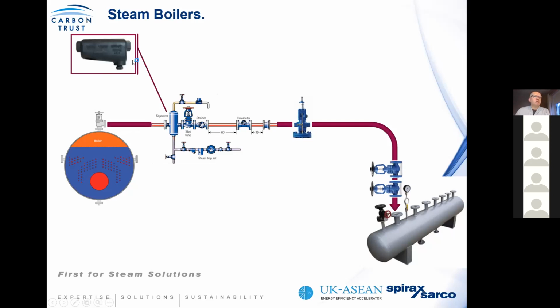What the separator does is that it removes the water that's generated from the boiler and carried over from the boilers within the steam before it gets out in the steam system. We always put in steam meters, but the problem is that we're not conditioning the steam in advance of the meter. And from our experience, we have found that steam meter data can sometimes be unreliable because the quality of steam that's supplied to it might not be the best. And steam can be corrosive if there's a lot of water entrained in it. So you're doing two functions. You're ensuring that you have very high quality steam to your distribution system, and you're protecting downstream plant.